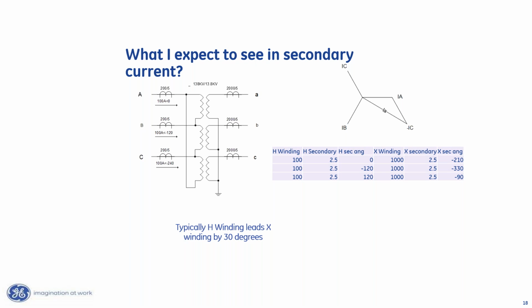So what that means is if I've got 100 amps flowing into the transformer at 0 degrees on the high side, I've got 1,000 amps flowing out of the transformer because of the transformation ratio. But because of my CT ratios, I've got 2.5 amps flowing into the relay from the CT on the high side and 2.5 amps flowing into the relay on the low side. Now, what that looks like is 0 degrees on the A phase high side and minus 210 on the low side. Now, what the relay actually does, we can think of this in a couple of different ways.